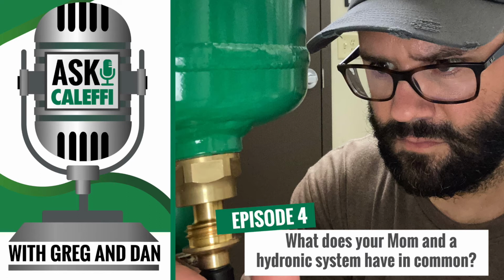Right. You're going to find that, if you're working with a dirty system and you install a dirt or magnetic separator, it may not be an annual maintenance thing to start with. You might be back once a day, once a week, maybe down to once a month, and then hopefully working it out to where you're doing annual maintenance and doing a flush on them. Absolutely. But we always recommend, if you know for a fact that the system is very dirty to begin with, before you install one of these, that you do a power flush on the system. Yep. Flush and clean, and then install this, and then do your water testing, and then add inhibitors as needed. Right, absolutely. Then you can use this to just finish cleaning up the system and then maintain it.